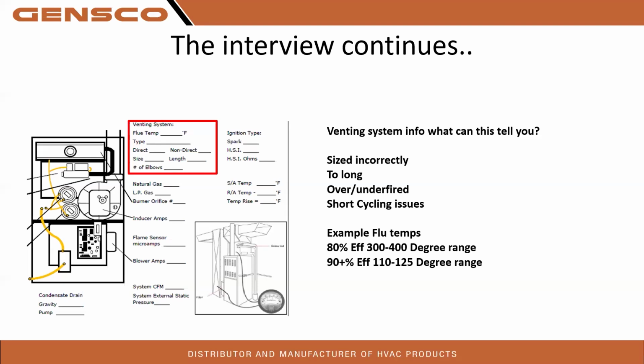So with PSC model inducer motors, we simply refer to the venting tables. With variable speed, we have switches and stuff that will have to be added as a kit. So this is all really good information to put in here. If you called me at Tech Services and said, hey, I've got this flue temp, I have these error codes, we can go back and look at the install guides and try to figure out, okay, that wasn't an allowable size, or too many elbows over so much length. Now we shouldn't be 2-inch, we should be 3-inch, depending on the application. So it can tell us a lot.